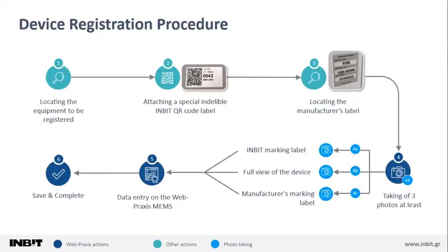I would like to briefly describe the registration procedure we followed for each device, starting with locating the equipment to be registered. After that, we attached a special indelible INBIT QR code label bearing a unique code on each device, then located the manufacturer's marking label. We took at least three photos of each device: one of the INBIT QR marking label, one of the manufacturer's marking label, and one full view of the device. This data would next be inputted into the WebPraxis Medical Equipment Management System. The whole procedure was specially designed to minimize time consumed in patient areas, patient discomfort, and distraction of medical, nursing, or administrative staff.